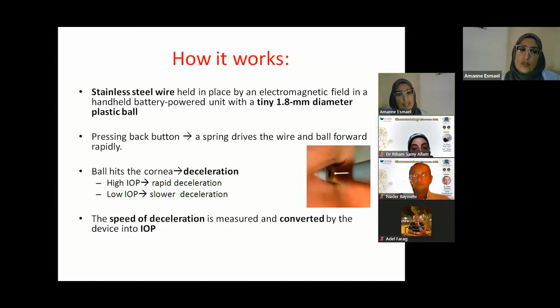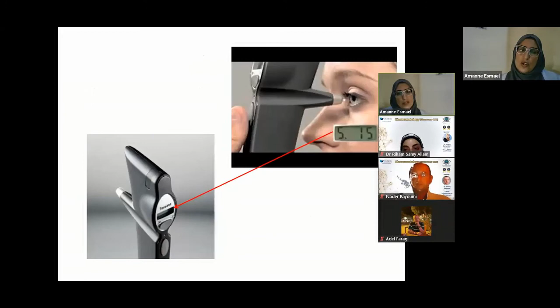Pressing the back button of the device will cause this wire to move forward. A spring drives the wire and the ball forward rapidly, and as it hits the cornea, it decelerates. The speed of deceleration is measured and converted by the device itself into an intraocular pressure reading that appears on the display screen at the back of the instrument.